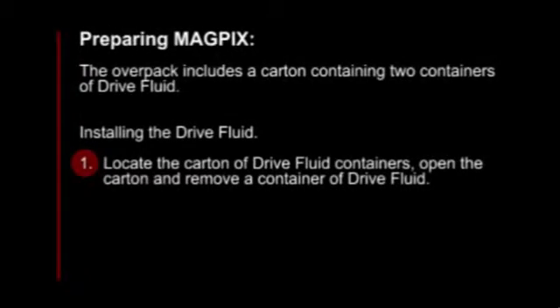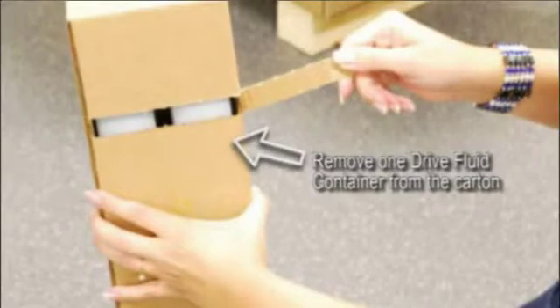The MagPix overpack also includes a carton containing two containers of Drive Fluid. To install the Drive Fluid, first, locate the carton of Drive Fluid containers.